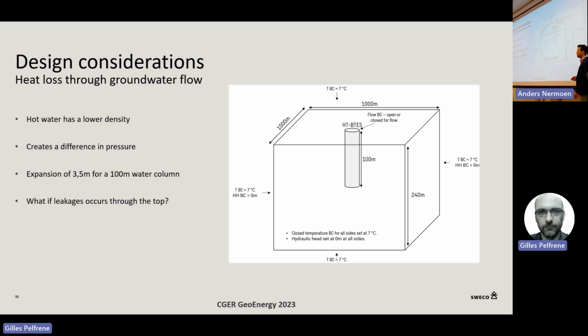In FEFLOW, we performed a simulation to find out what we can expect in terms of groundwater losses. To give you an idea, if you have a 100-meter borehole with a 100-meter water column, which is the case in this project, we have a bit of artesian flow, so the groundwater reaches all the way to the top. If we heat that 100-meter water column, which is 10 degrees at the start, up to 95 degrees, it would rise by 3.5 meters. It becomes lower in density, meaning a bit less pressure, and especially if water leaves at the top, it has to be replenished from the bottom, which can be a big driver for leakage and thermal losses.